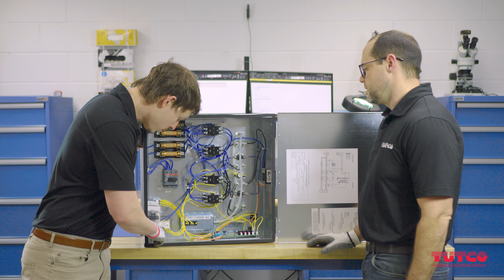I think I actually have one right here. Excellent. So you mentioned not only the room thermostat, but a duct probe as well? That's right. We'll place those inside the box, usually taped to the wall of the enclosure, available for the installer to use. The duct probe goes either upstream or downstream, depending on how you want to use the stat, and the thermostat can be wall mounted to let you adjust your set point.